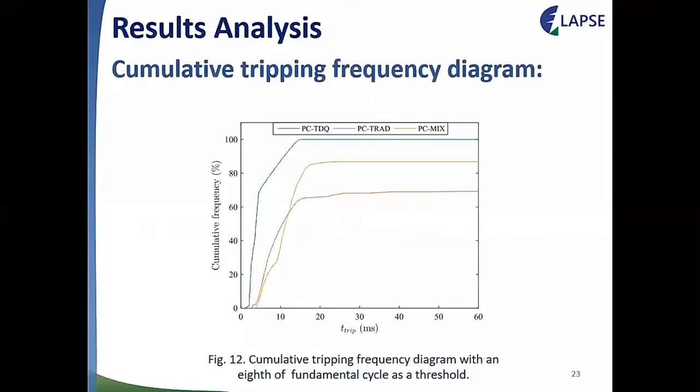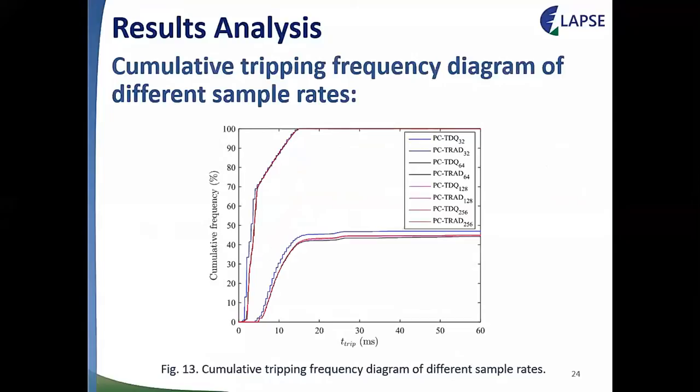To better compare the functions for the same cases, simulations were also carried out using a threshold of one-eighth of a cycle for all analyzed functions. It can be seen that the traditional PC protections had superior performance with a lower threshold, but the literature suggests using one-quarter cycle for safe operation, avoiding improper operation in adverse cases. Thus, these results prove the effectiveness of the proposed function, showing its safety and confirming that the TDQ approach indeed reduced tripping time.